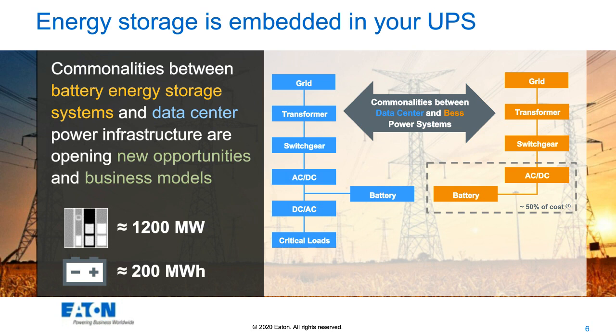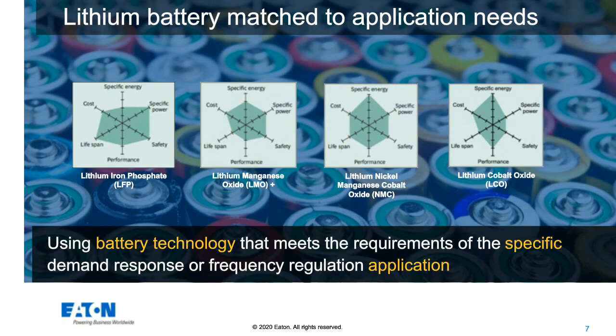And by the way, none of this would really be viable without the advent of lithium batteries. And lithium batteries are used now with UPSs, not just because they're smaller and lighter, and they are, but they also have a much longer service life in a UPS application, 10 to 15 years. They may last as long as the entire UPS system does.